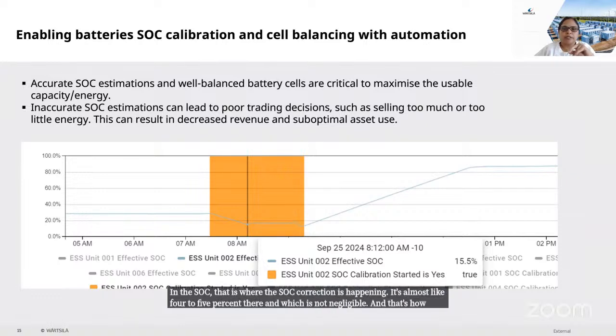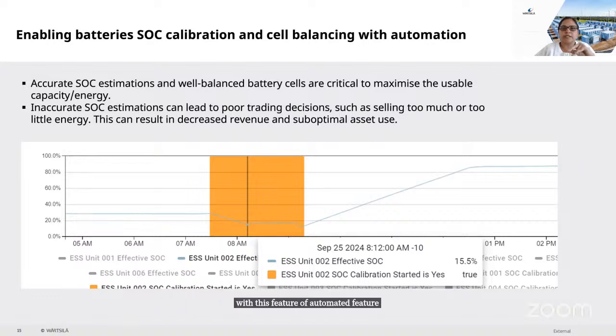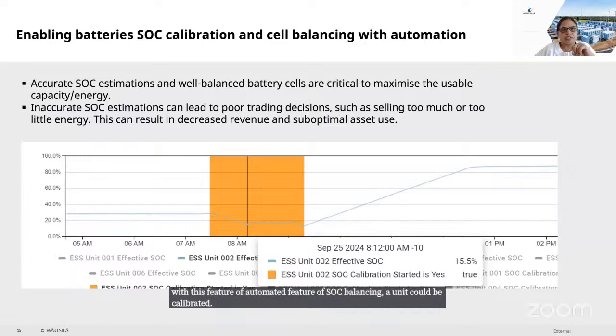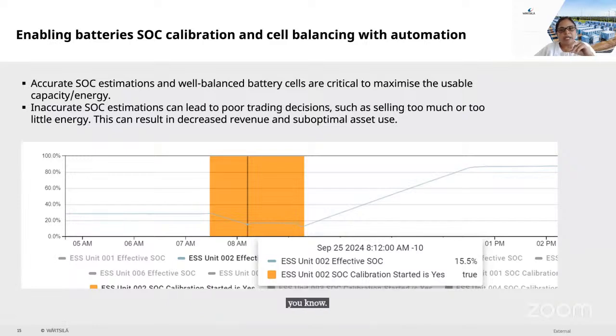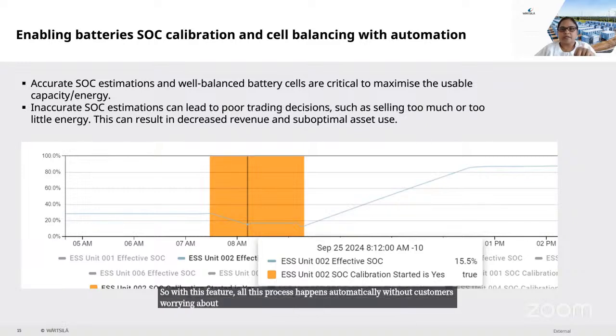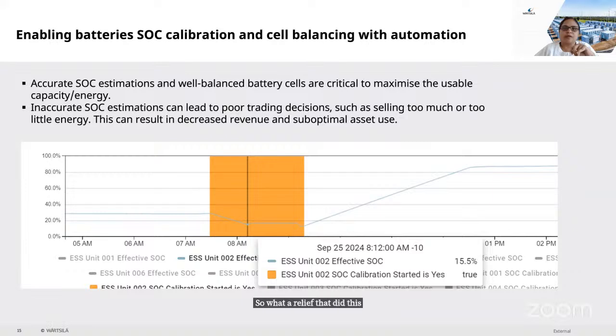And that's how, with this automated SOC balancing feature, a unit could be calibrated. Without this auto steering, the customer's operator needs to manually put these units through all these steps to calibrate them and balance the cells. You can imagine how much effort and expense that could be for large scale utility sites, to gain the benefit of a well-balanced and regularly calibrated site. With this feature, all this process happens automatically without customers worrying about calibration and balancing of the batteries. So what a relief this automated feature gives to the customers. Next slide, please.